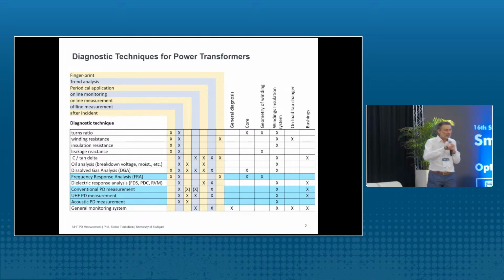For an offline method, you have to disconnect the transformer from the network, and then you do the measurements, and after the measurements you have to reconnect the transformer. So let's say the result is just the situation at this moment, which is normally, of course, not under load, just under voltage, but you do not have load on the transformer. And the big disadvantage is, of course, you have to disconnect and switch off the transformer. This is often a problem, because these transformers are needed, and so offline measurements are sometimes difficult to perform.